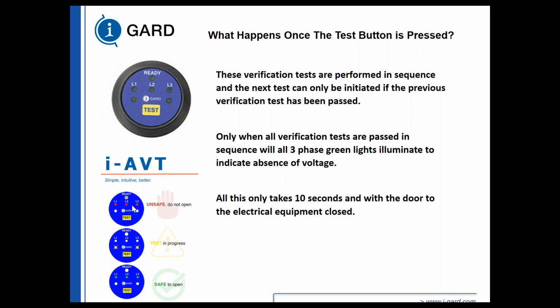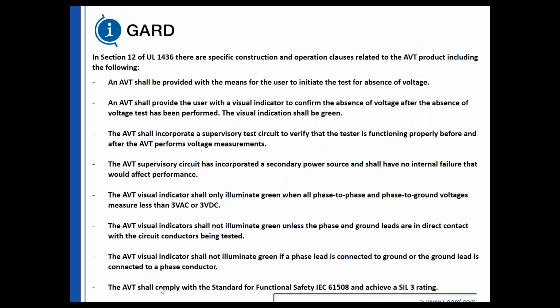So 3 red LEDs, it's unsafe. Do not open the door. Or only qualified people should open the door and perform what testing they need to be done. But you have to wear proper PPE at that point in time. If you have 2 flashing amber lights, the test is in progress after you've pressed the test button. 3 green LEDs, it's safe to open the door and it's de-energized where it's connected. And we verified that the connection is good.